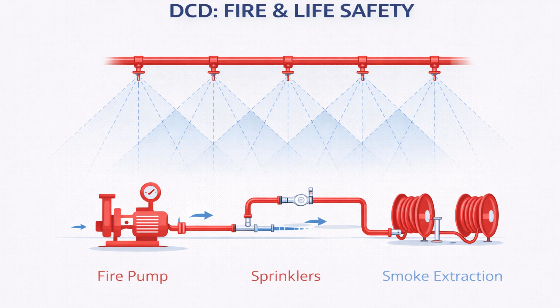Now let's talk about what Dubai Civil Defense actually checks. With Dubai Civil Defense, drawings alone are not enough. DCD starts with engineering logic. The first thing they look for is hydraulic calculations. They want to see flow rates, pressure losses, critical path analysis, worst case demand scenarios. If hydraulic calculations are missing or not clearly justified, the submission stops. Next, they check pump redundancy. DCD does not accept single point failure. They expect duty and standby fire pumps, reliable changeover, compliance with failure scenarios.